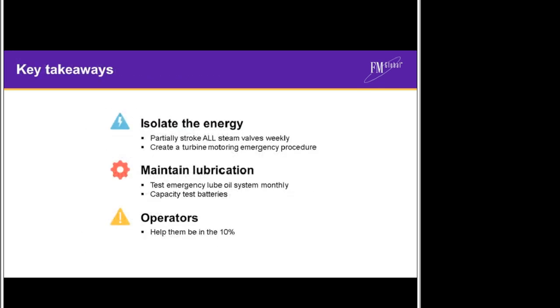To recap, three takeaways from today's discussion on steam turbine safety devices are, firstly, that all of the energy should be isolated from the steam turbine. To do this, steam valves should be partially stroked on a weekly basis to ensure that they're going to isolate steam if required, and a turbine motoring emergency procedure should be developed to maximize the chance of an operator being able to successfully intervene in a turbine motoring event.